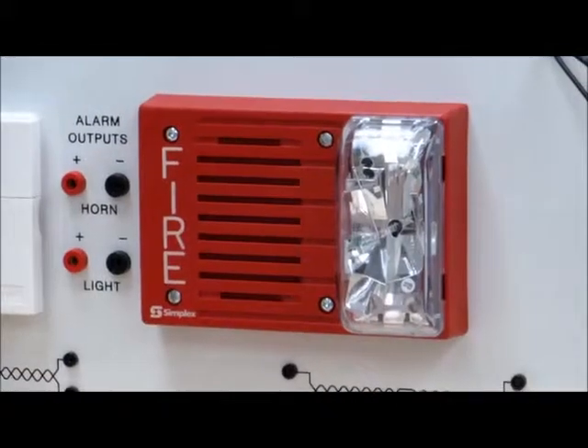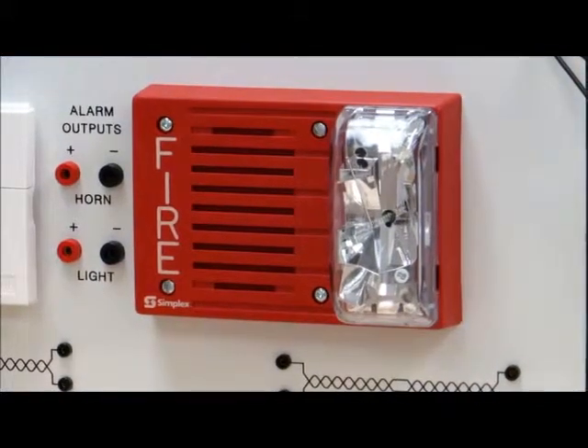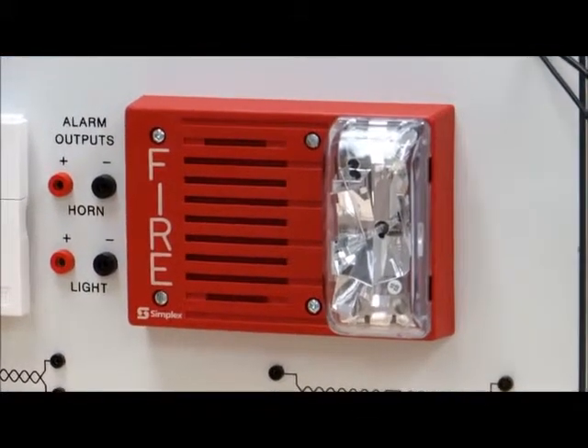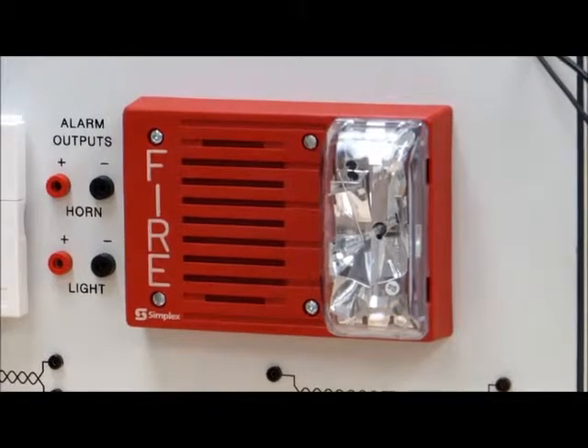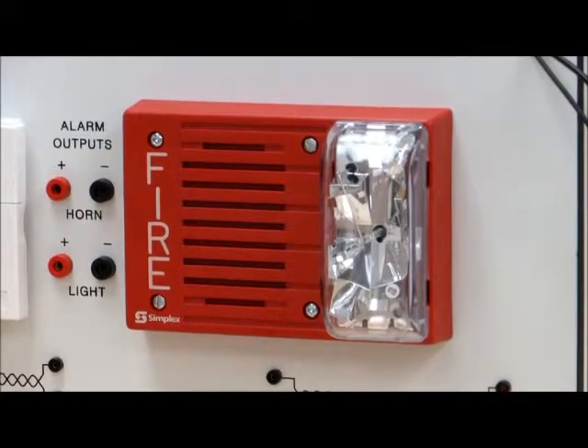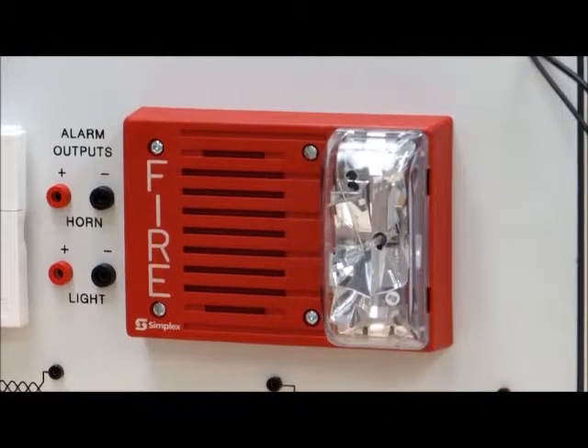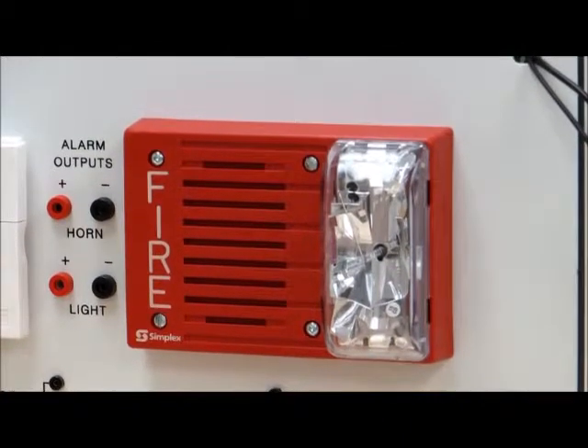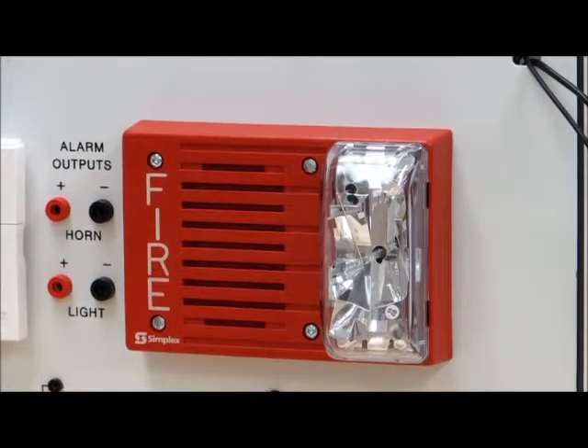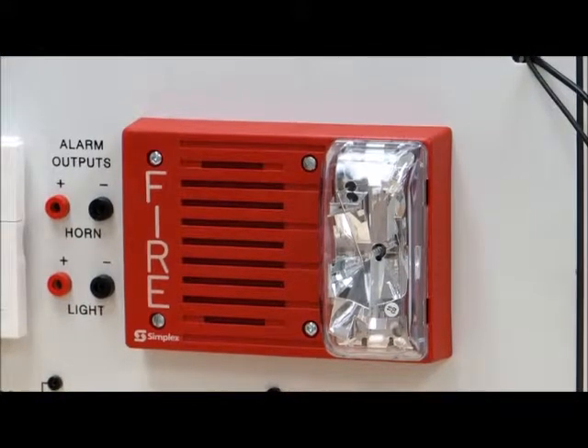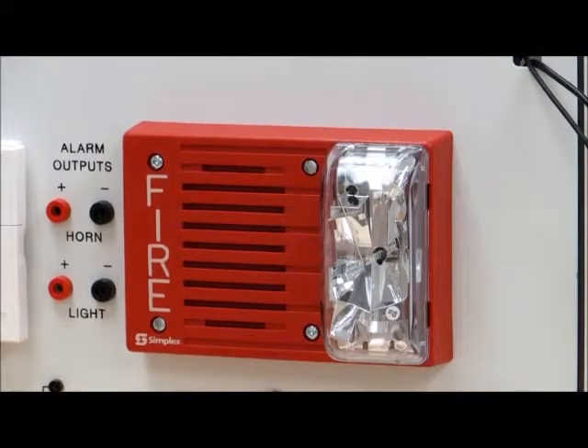The fire alarm does not talk over the network. It just has analog outputs that talk with the I/O modules that do talk with the network. It has an alarm output and a horn output. The alarm output and horn output a 10-volt signal that can be read through the analog modules.